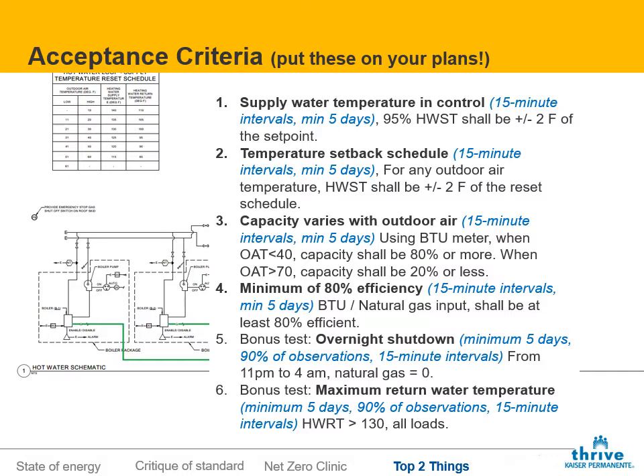Fourth, we want to see efficiency. We actually want to see and measure efficiency. Efficiency is measured by looking at the system demand, which is that GPM delta T, and then comparing it to the natural gas input.